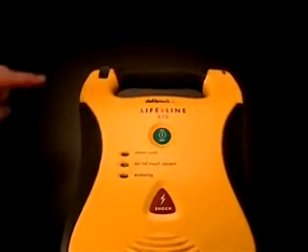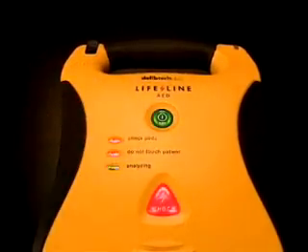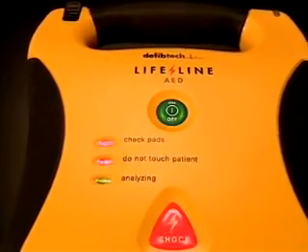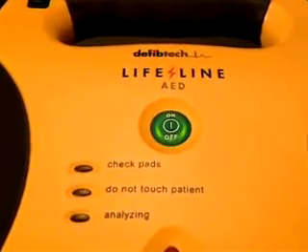When a 9-volt battery is installed in the battery pack, the AED will automatically run self-tests on a regular basis. However, there may be times when the user will want to run manually initiated self-tests. To run a manually initiated extended self-test, begin with the unit off and press and hold the on-off button for 5 seconds until the unit announces it has entered the self-test mode. The unit will run a complete extended self-test, report its status, and automatically turn off. Be aware that running a manual self-test uses one shock's worth of energy from the battery pack.